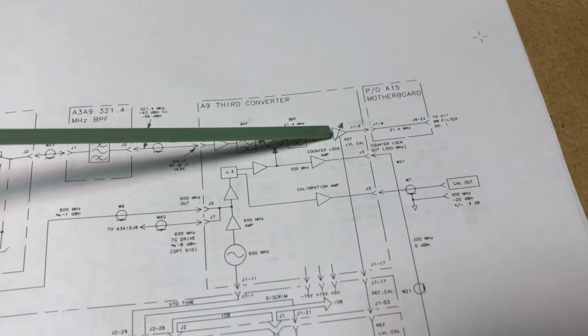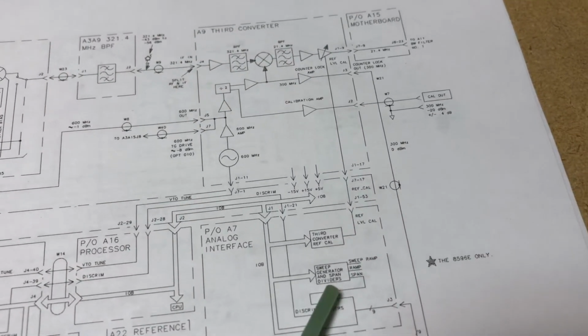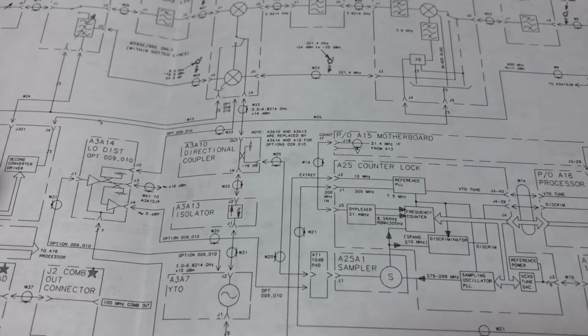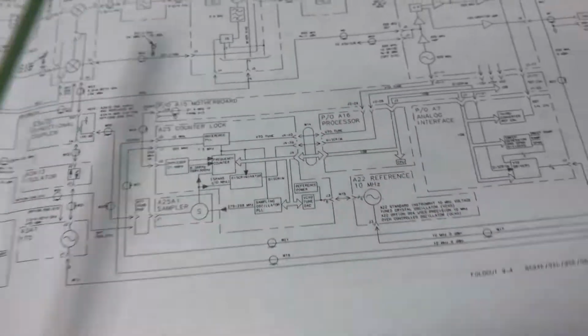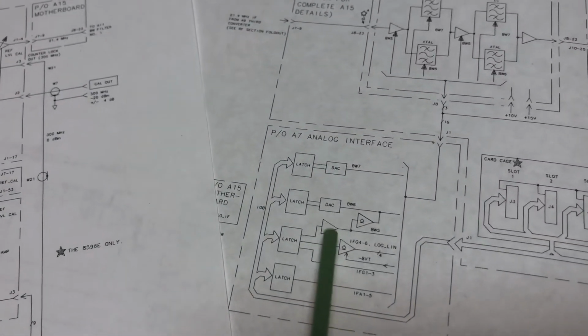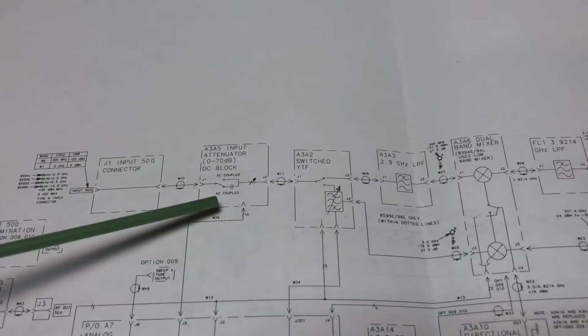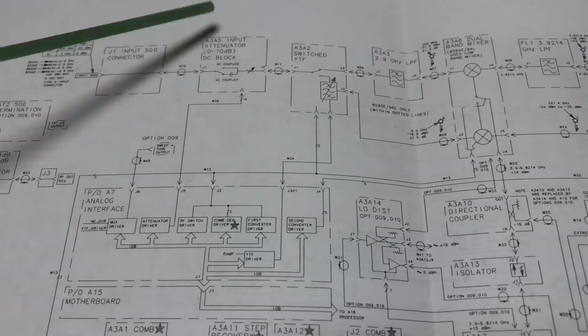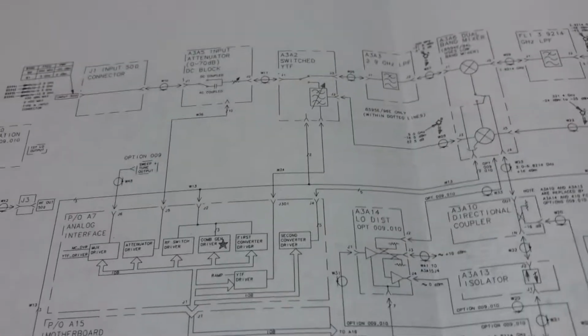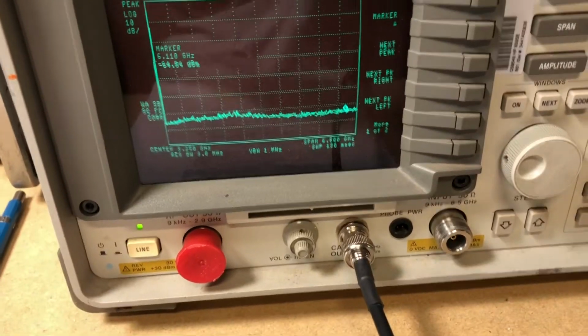But it uses all of the calibration data to adjust these DACs. Here's the reference level cal here, part of the cal amplitude. There's the DAC for it there, and there's other DACs in here that do things with the amplitude control. There's a lot of the DACs are on the A7 analog interface here. There's controls for frequency flatness. There's DACs to control the attenuator blocks to adjust the attenuator pads to make them have a sort of flat and even response. There's all sorts of things, but the first thing we'll do is I'm going to run the amplitude cal and the frequency cal on the unit. All right, so let's check the cal out signal.